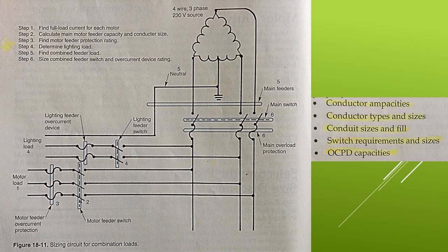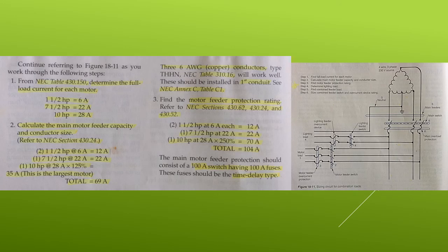Using the step-by-step method, the procedures that follow illustrate how to find the values needed. Every electrician should master this step-by-step procedure because it is quick and practical. Furthermore, the method can be applied to many power lighting combination circuits. Step 1, from NEC table 430.150, determine the full load current for each motor. For the 1.5 horsepower, we have 6 amps. For the 7.5 horsepower, we have 22 amps. And for the 10 horsepower, we have 28 amps.